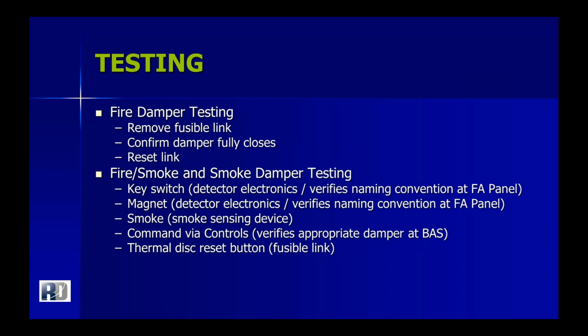From a code perspective, before occupancy, and this the AHJ usually participates in, they need to test with smoke. So it could be smoke through the detector itself, or it could be smoke in the duct at the wand. If you're just looking to see the damper fully open and fully closed and the controls are controlling them, you could command them open and close.